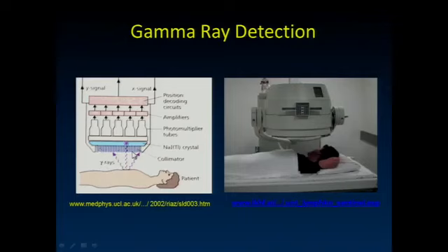So it's really the collimator that, if you will, acts as the lens to focus the radiation so that we're only accepting it along a particular direction. Beneath that is our sodium iodide crystal. When one of these gamma rays interacts in the crystal, we're going to get the production of lower energy visible light, which is going to be readily detected by our photomultiplier tubes. Unlike our X-ray imaging, we're going to have really tiny detector elements because we need really high resolution imaging.